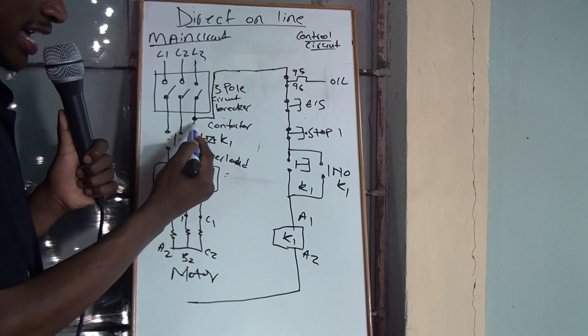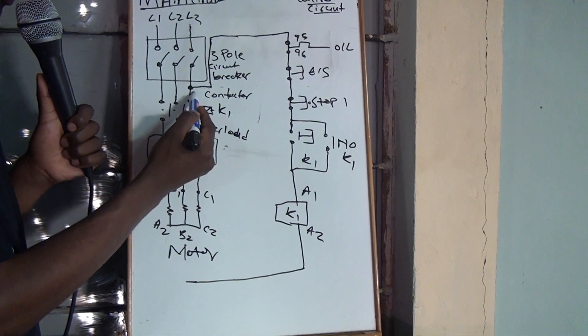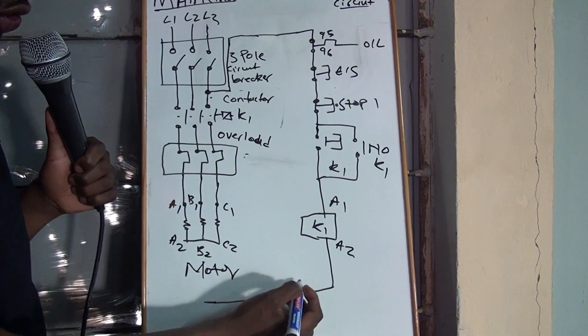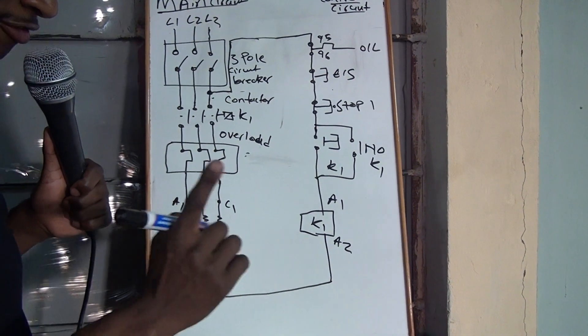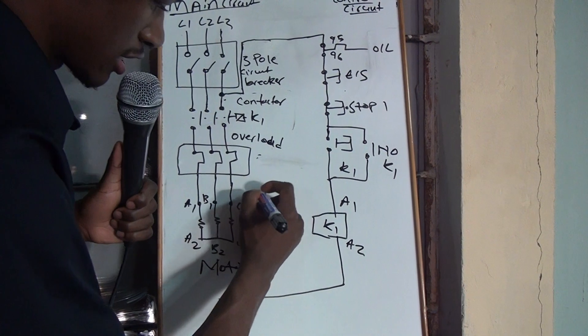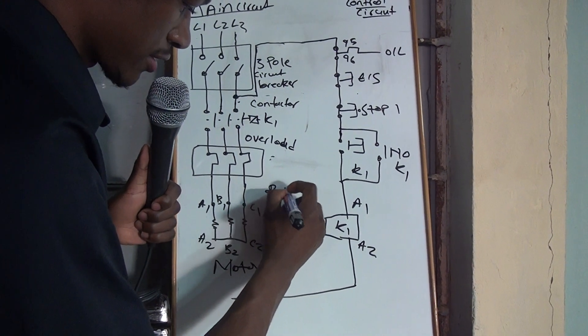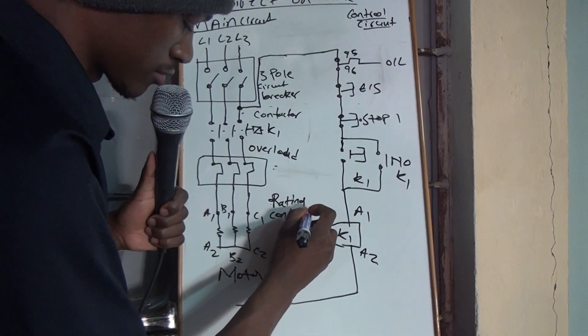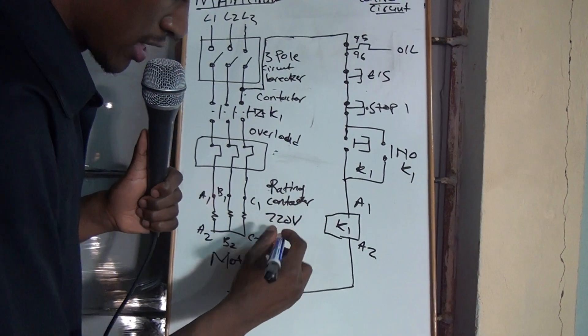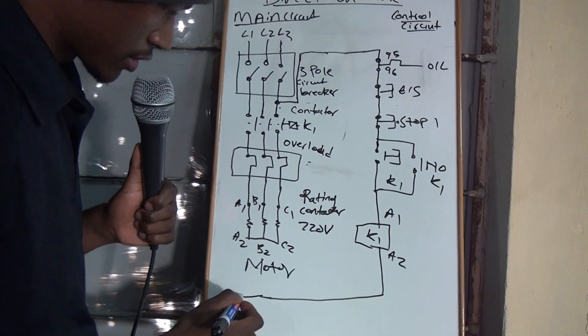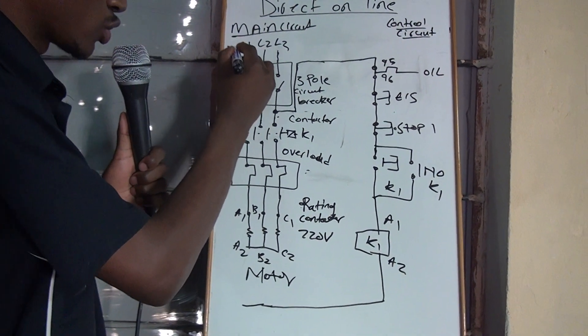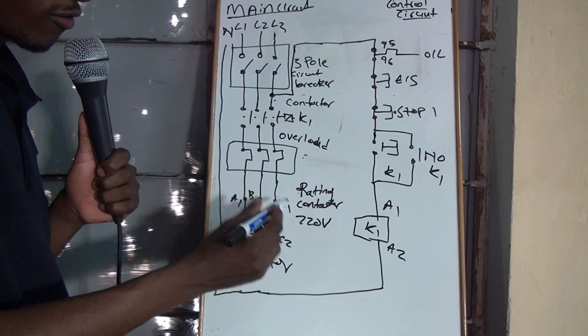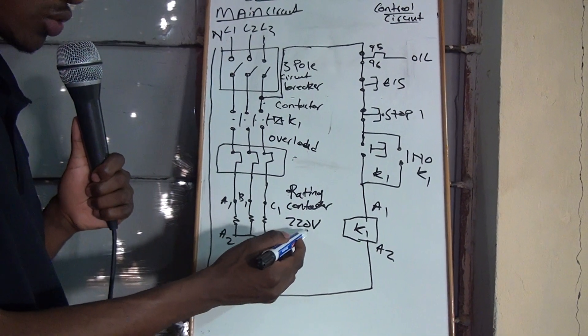So, your line 3, you put it on line 3, but after the circuit breaker. And then, when you connect your A2, if the rating of your contactor is 220 volts, it means that you'll return this to neutral. So, you'll introduce a neutral. Then, your neutral comes here. That's because the rating of the contactor is 220 volts.